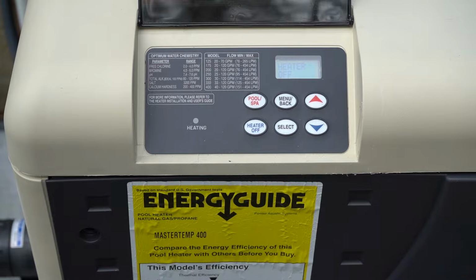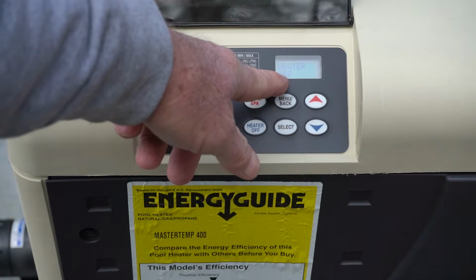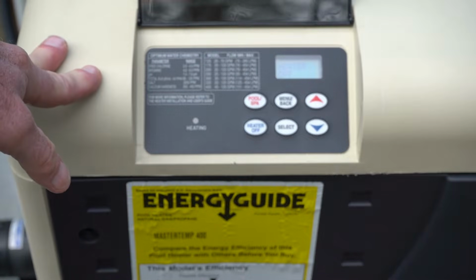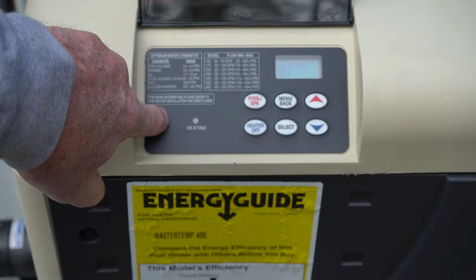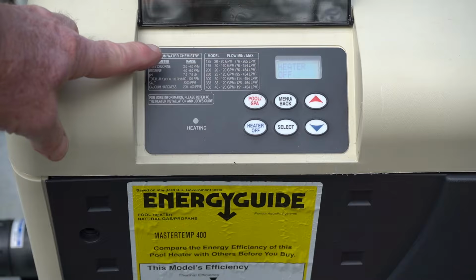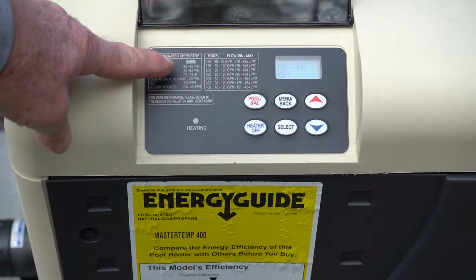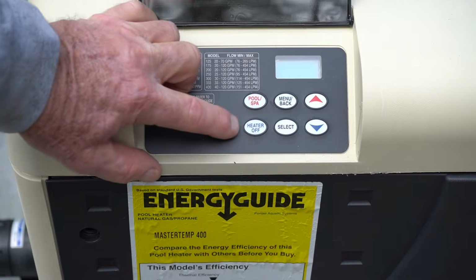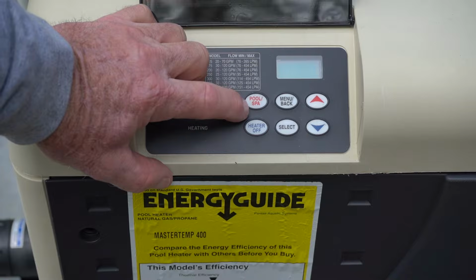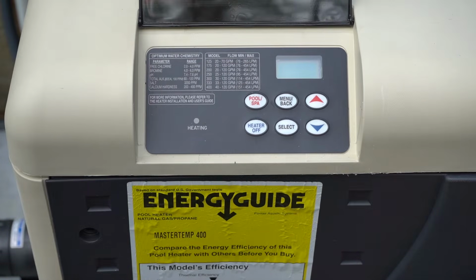Today we have a video for you about the stack flue sensor. There's a number of errors. You can get E01, E05, and of course one says that the stack flue sensor is open, the other one says the stack flue sensor is shorted. But then you have the other situation that happens, and on the new control panel it would come up with an error and it says stack flue sensor if the heater got shut off by that. And if you have the old control panel, there's a red light on the bottom of it that would be next to the SFS LED, and that way you would know that the stack flue sensor is what caused it to fail. So what causes this?